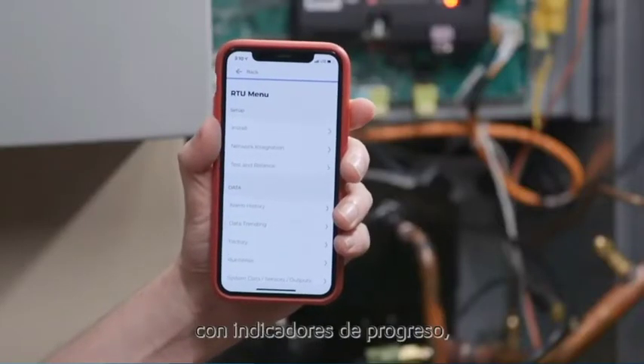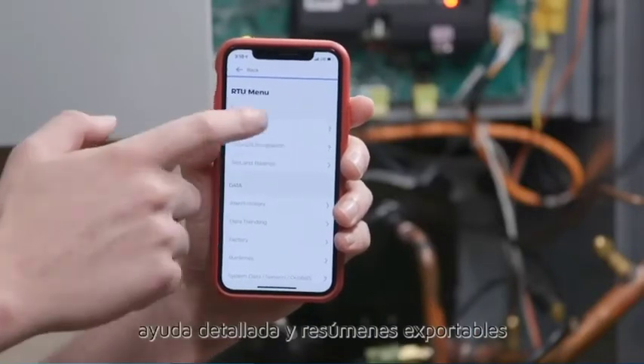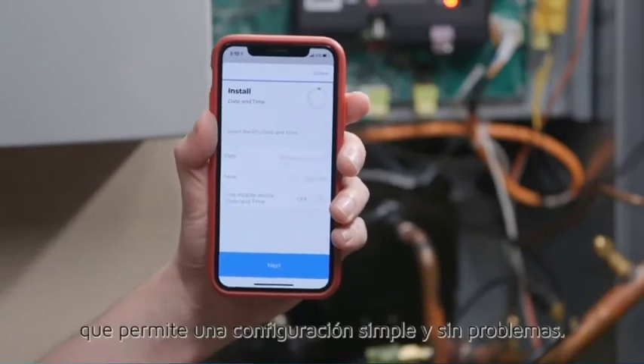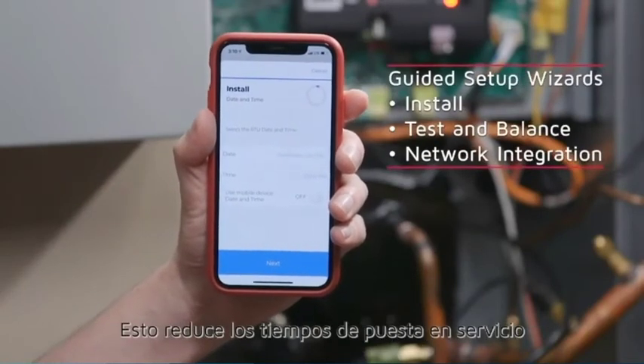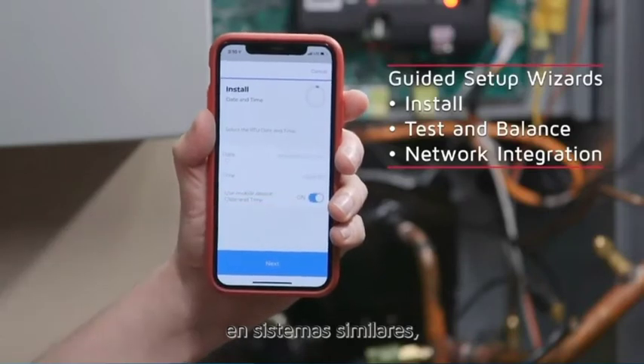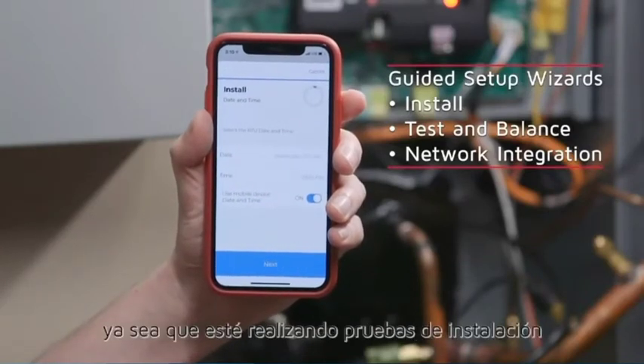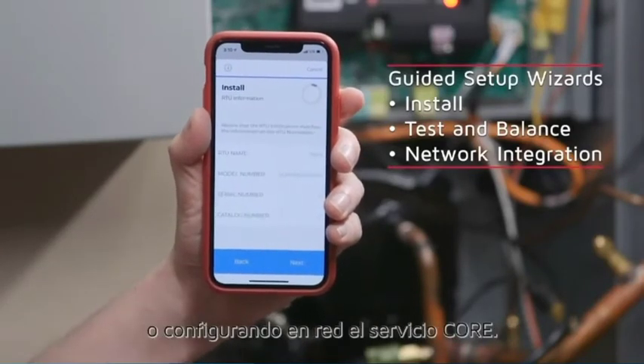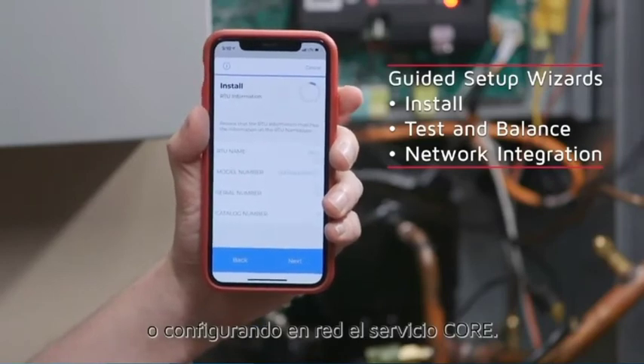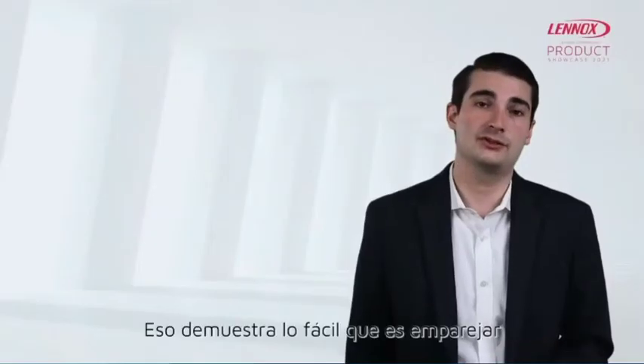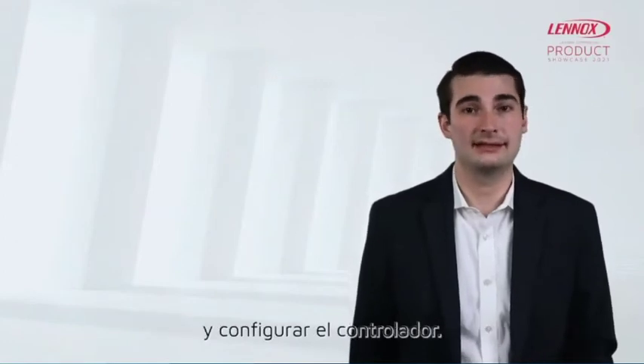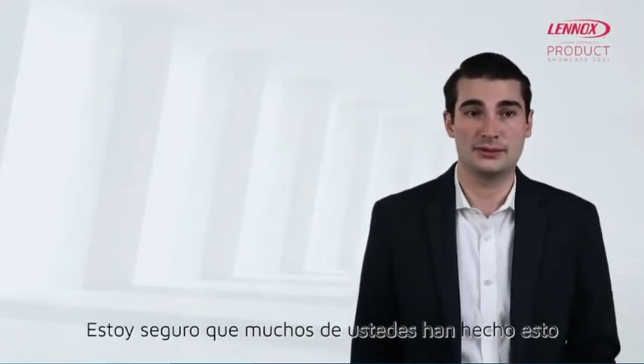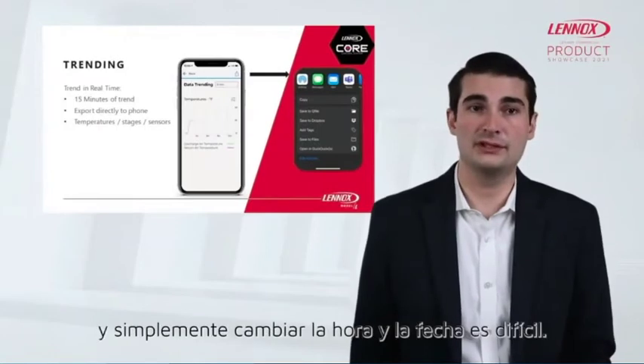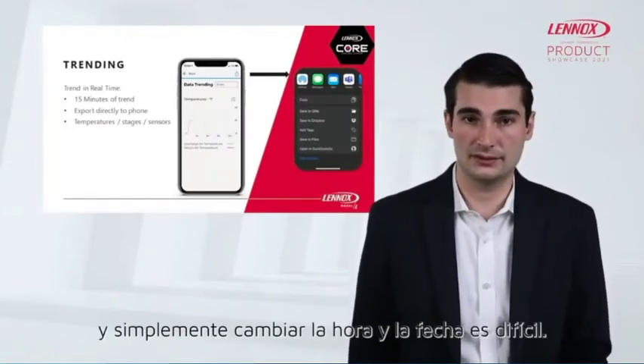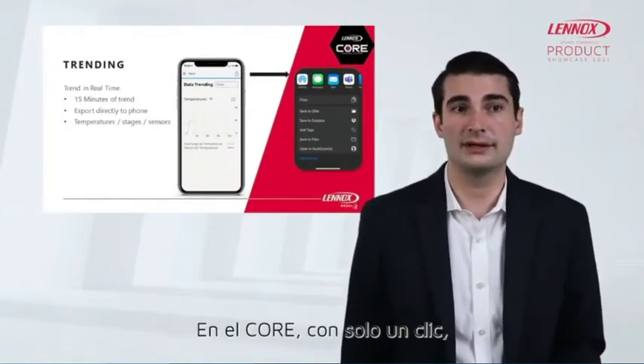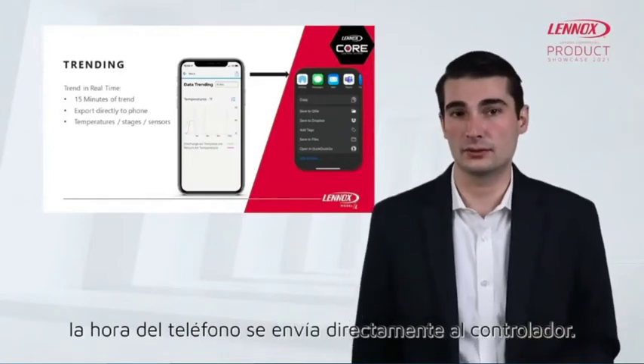Guided setup with progress indicators, detailed help, and exportable summaries drive simple and trouble-free setup, reducing commissioning times over similar systems. Whether you're doing unit installation, test and balance, or network setup, the core service app will be there to guide you. That shows just how easy pairing and setting up the controller can be. Sure, many of you have done this in the field, but simply changing the time and date on some controllers is difficult. With Core, one click of the button and the phone's time is sent directly to the controller.